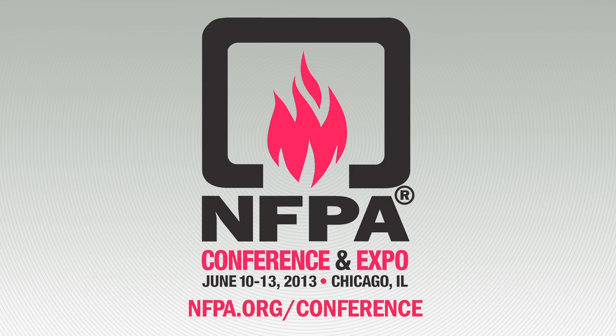The data generated will be placed into a report. There is already a report covering the first six tests, and a report for this last test will be written for the Fire Protection Research Foundation. That data will be submitted to the NFPA technical committees for their consideration in developing sprinkler system design criteria for inclusion into NFPA 13, which currently doesn't have that criteria for exposed expanded plastics placed in racks.